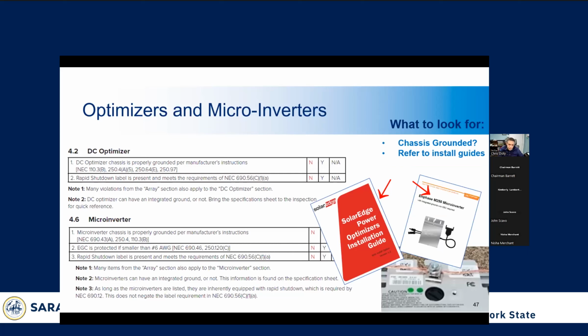A very important element of installing and inspecting this type of equipment is a thorough understanding of the installation manual. That may include specific considerations for that device, right? It could be how you mount it to wherever it's mounted, or specific bonding and grounding requirements, or limitations on string configurations, things like that. So you may have to look through the installation manual to get those specific requirements. But if you want to have a safe code compliant system, it's worth it to obtain those and look through them.